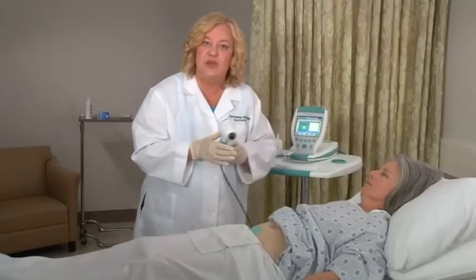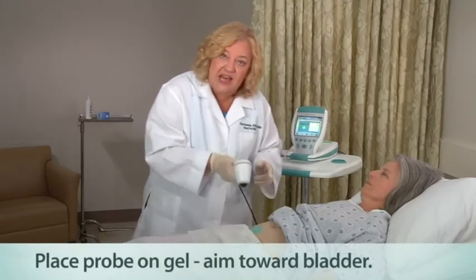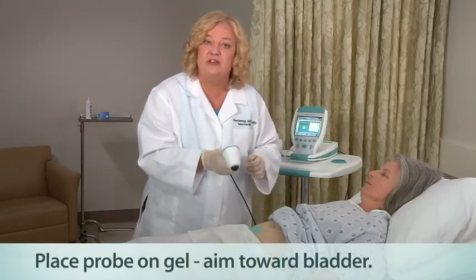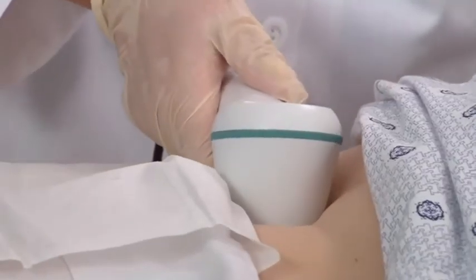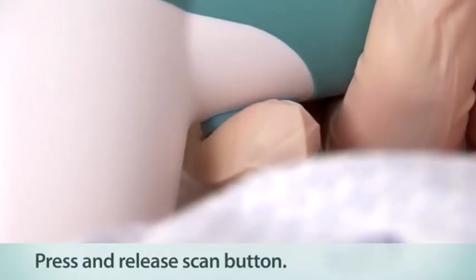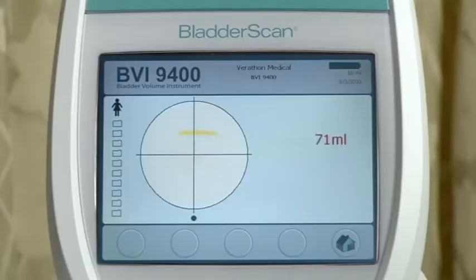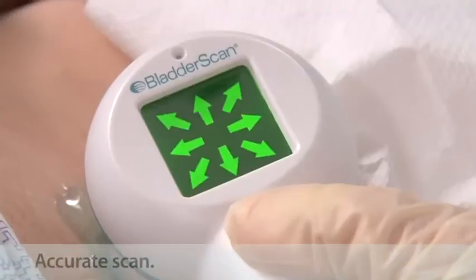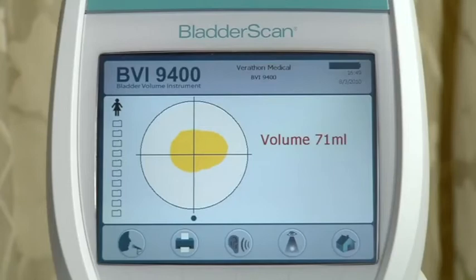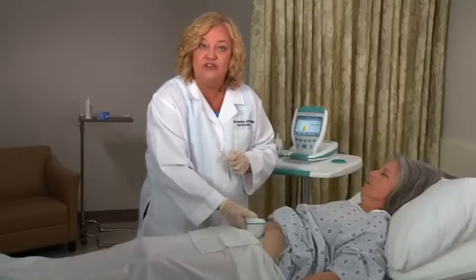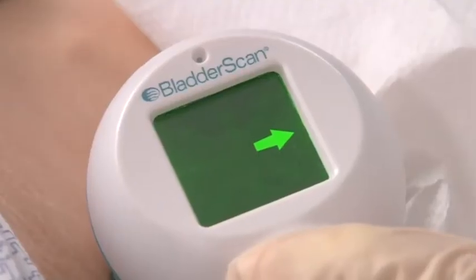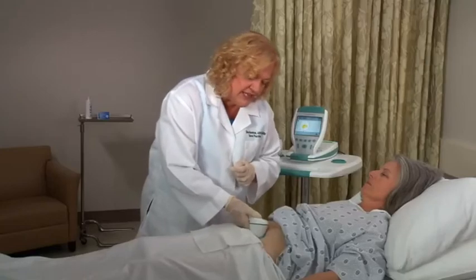Standing alongside the patient's right side, place the probe on the gel and aim downward behind the pubic bone towards the expected location of the bladder. Press and release the scan button, located on the underside of the probe. When you hear a beep, the scan is complete and a bladder volume measurement is displayed on the console. You know the aim is accurate when you see all 8 arrows are flashing on the probe, and the bladder image is centered in the crosshairs of the console's aiming icon. If the scan is off target, the arrows on the probe indicate the direction of the bladder. Look at the position of the probe, and using these arrows, re-aim the probe for a more accurate scan.